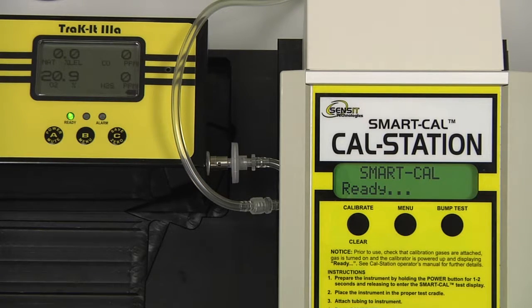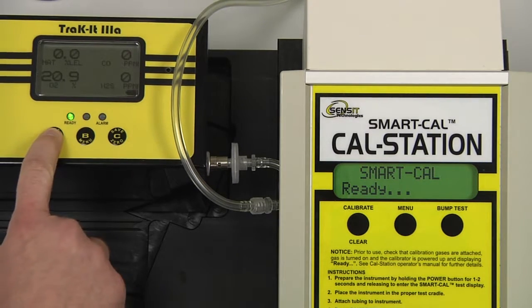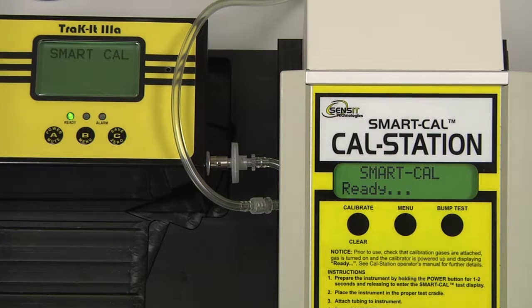To begin the calibration process, enter into SMART-CAL mode on the instrument by pressing and holding the A button for approximately 2 seconds and releasing. SMART-CAL will be displayed. On the cal station, press and release the calibrate button. We will have an indication that the device has been found. A flow check will be performed, followed by a 60-second purge. After the purge is complete, the instrument will auto-zero and the calibration process will begin.